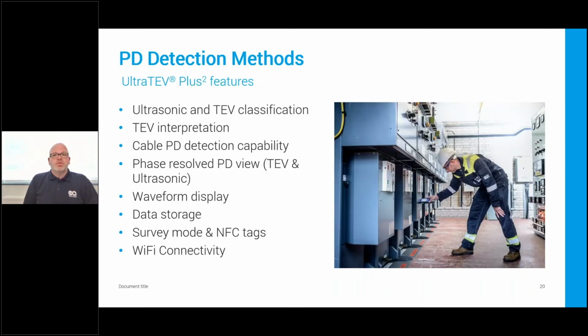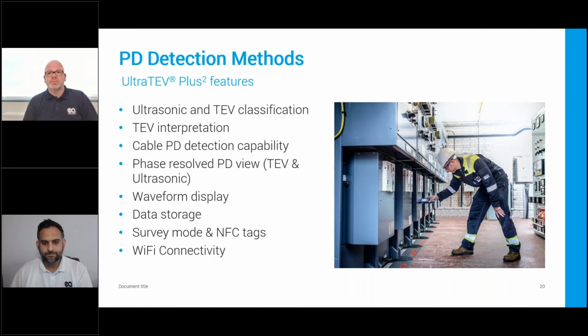So onto the UltraTEV Plus 2. Now this is the next level instrument up from the detector. Obviously you've got the capability of looking for TEV and ultrasonics, but this time you get an actual real-time display of the levels of PD. It also gives you a phase plot or phase resolved PD pattern, so a visual representation of the PD activity.